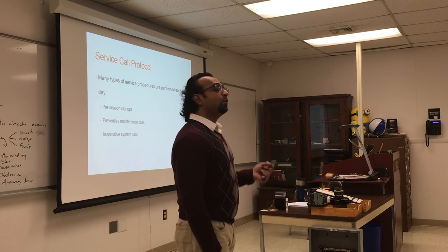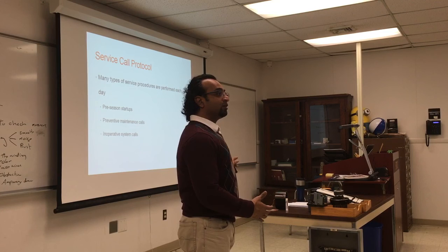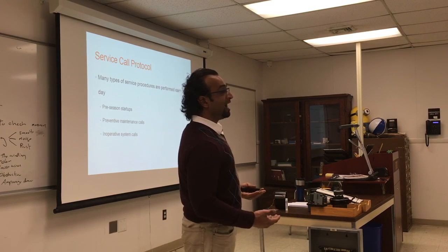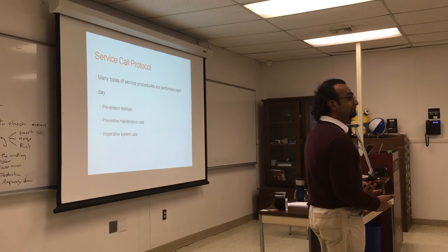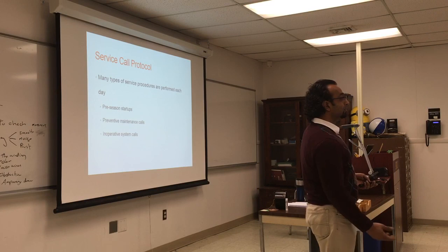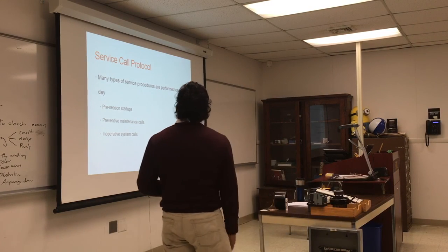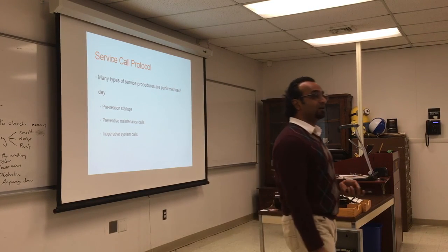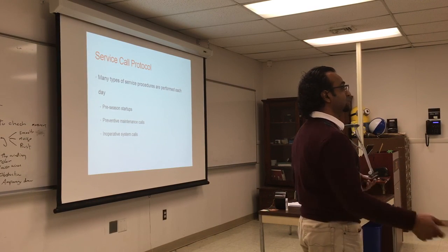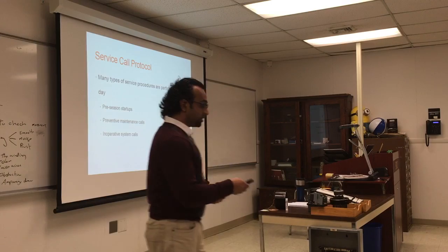And again, with oil, if it's a separated system, it's going to be simpler. Now they're getting more and more complicated. There's big boards with a lot of wires in it. I find it sometimes intimidating. But again, just take a breath and look at the paper and see what is going where. And sometimes it's easier just to change the board. The boards are not that expensive. You can change the board for like $60 and just plug in the wires where they're supposed to go.